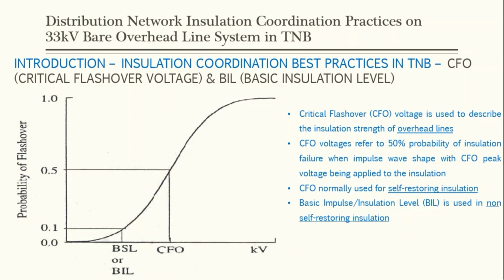Why is that? For the bare medium voltage overhead line, we call it CFO instead of BIL, because the main insulation for our bare medium voltage overhead line is air. So air is self-restoring insulation. But we also have solid insulation, which is also known as non-self-restoring insulation, and this is what we use when we talk about basic impulse or basic insulation level. So the solid insulation would include glass disc insulator, porcelain for example, or even composite material. So we also have solid insulation plus the air as the main insulation for overhead lines. That's why we need to coordinate between the air insulation and solid insulation.